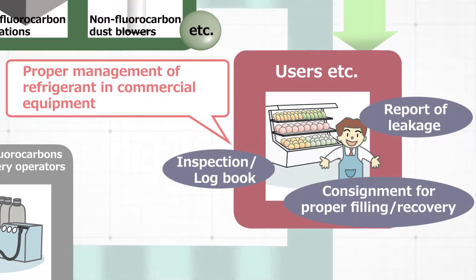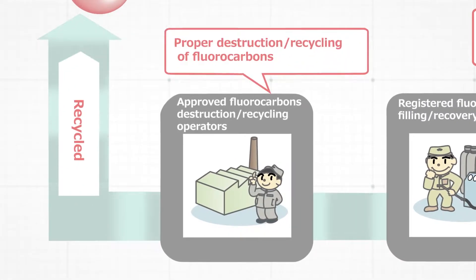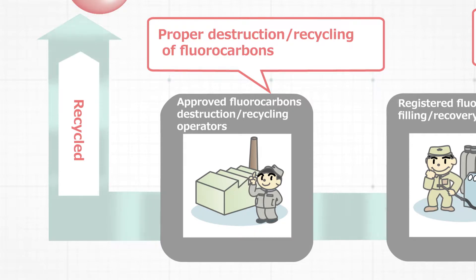Users of commercial refrigerators, freezers, and air conditioning equipment using fluorocarbon are required to maintain a practice of equipment inspection and reporting, consignment of appropriate filling or recovery of fluorocarbon, and reporting fluorocarbon leakage to related ministries when leakage exceeds a certain amount. Approved filling and recovery operators must fill and recover fluorocarbon in accordance with national criteria, and if not recycling it themselves, must deliver it to a recycling or destruction operator. Approved destruction or recycling operators are required to recycle and destruct fluorocarbon in accordance with national criteria and regulations.